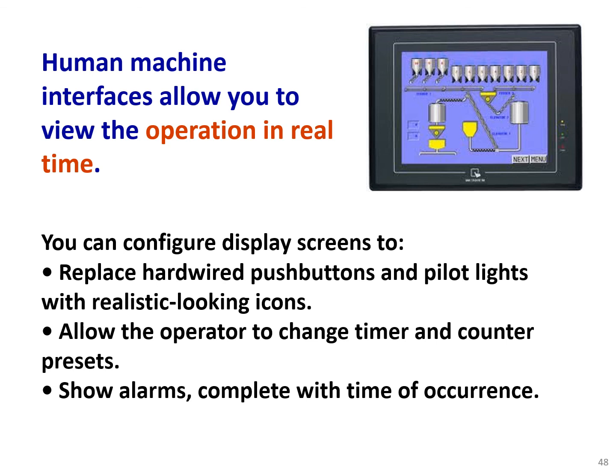Human machine interfaces allow you to monitor the operation in real time — you can see the visualization and observe what's going on online and in real time inside the process. You can configure display screens to replace hardwired push buttons and pilot lights with realistic-looking icons, allow the operator to change timer and counter presets, and show alarms complete with the time of occurrence.